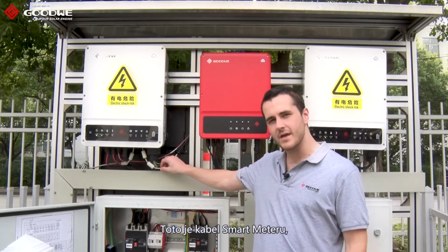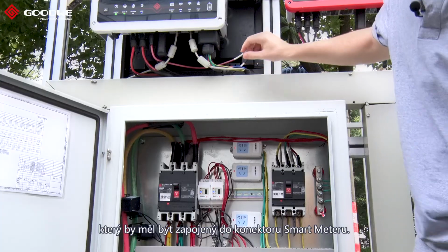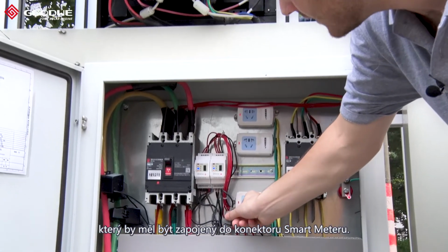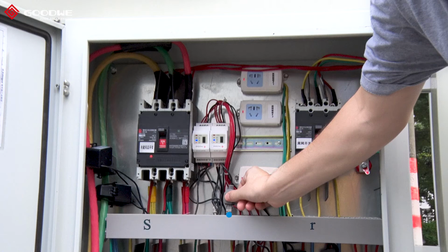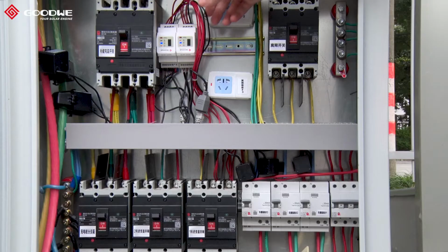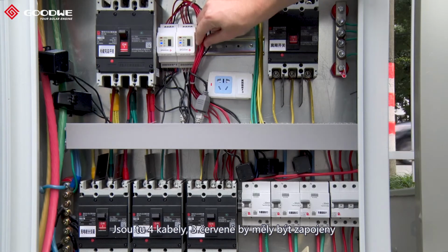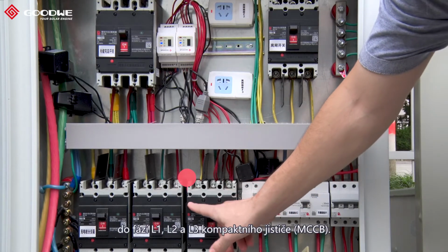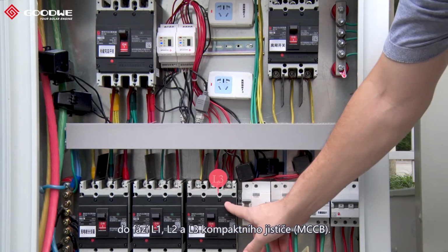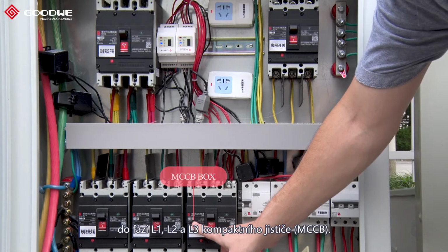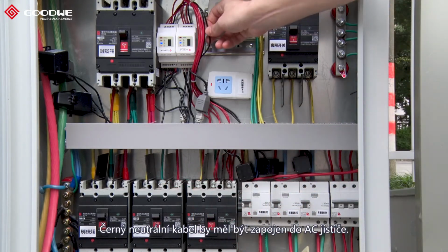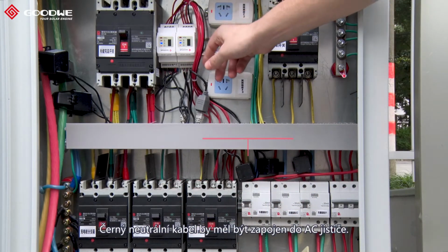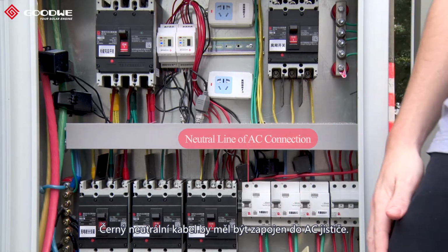This is the smart meter cable, and the smart meter cable should be connected right here to the smart meter connector. There are 4 cables, and the 3 red ones should connect to the L1, L2 and L3 phase of the MCCB box. And the black neutral cable should be connected to the neutral line of the AC connection.